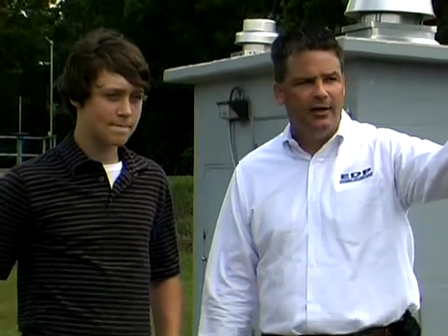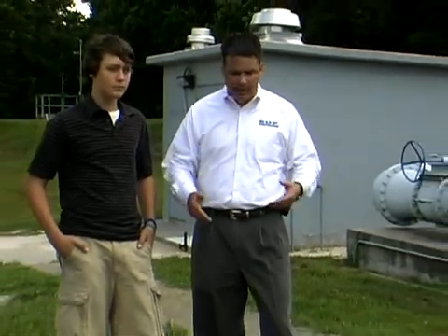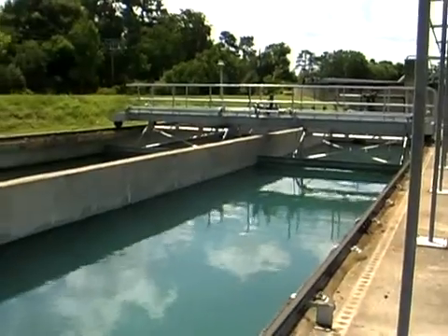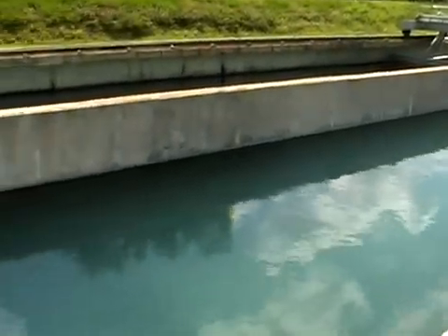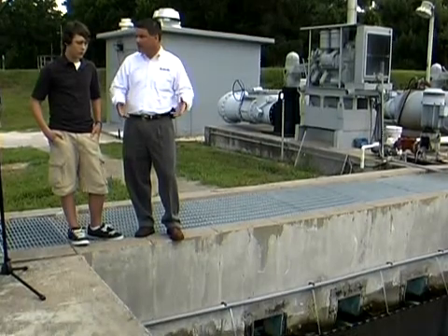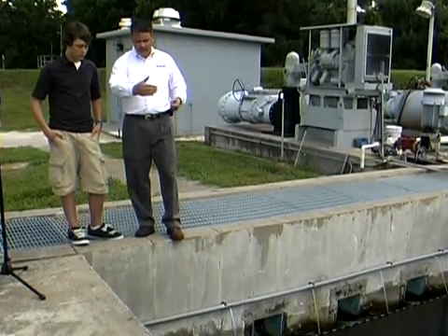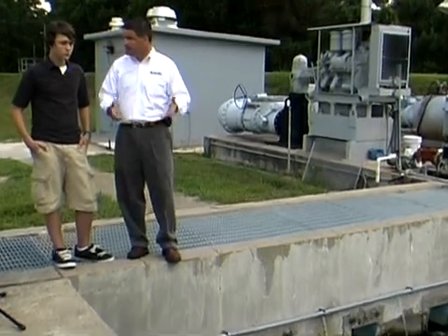Well, in this tank we've added chlorine at the beginning of the tank. The chlorine sits in this tank with the water in contact for maybe an hour and a half to 2 hours. That's to kill any residual bacteria that are left over after the treatment process. So I told you that we settle the bacteria out in the clarifiers. Not all of the bacteria gets settled out. A lot of it stays in the water, so we want to remove as much of that as we can. So we add chlorine, it comes in contact with the bacteria. Most of the bacteria die, but not all of it, since we're just disinfecting it.